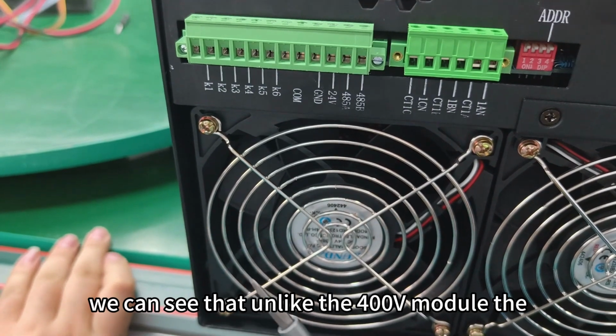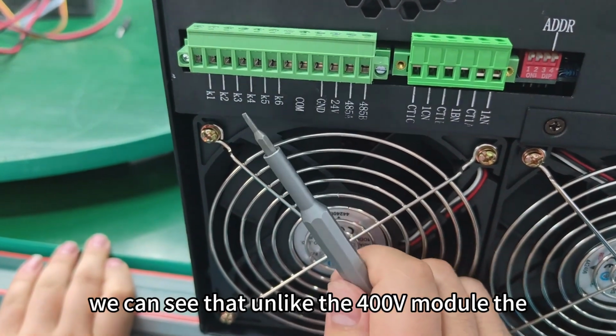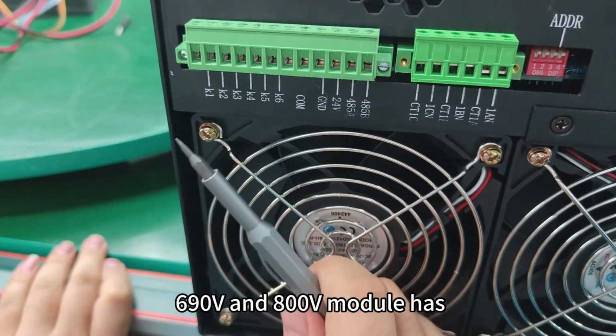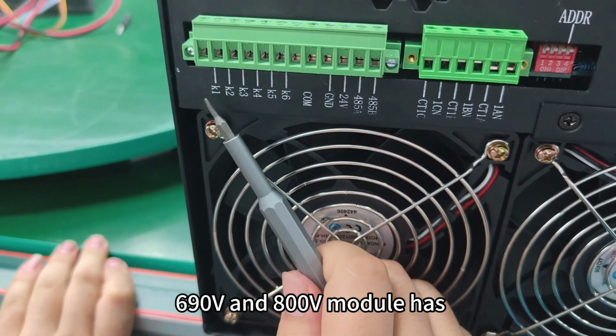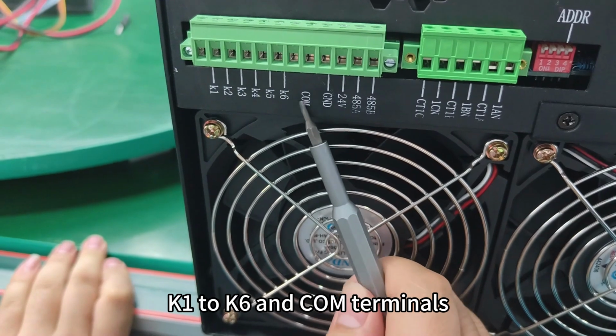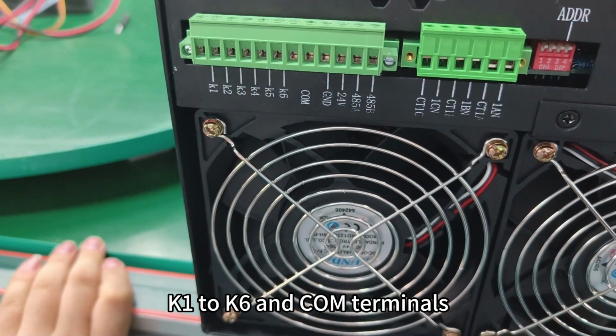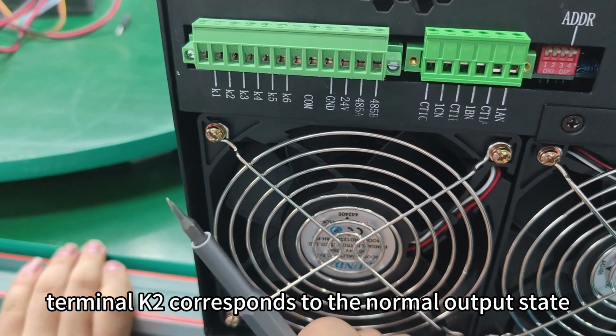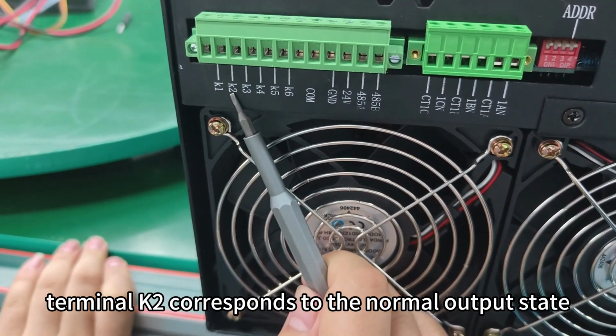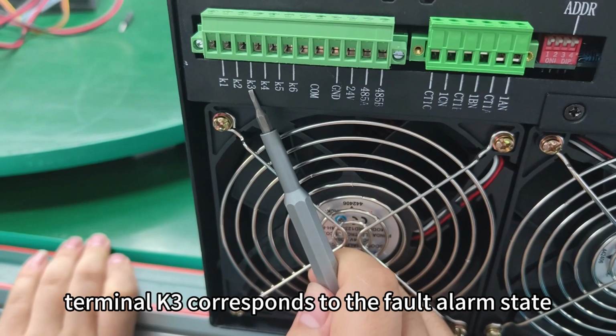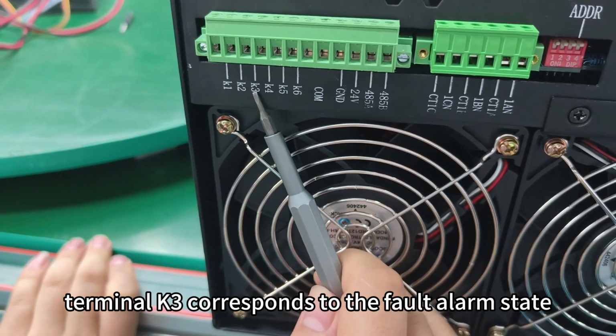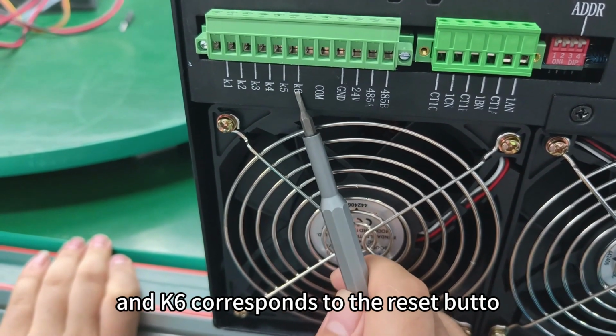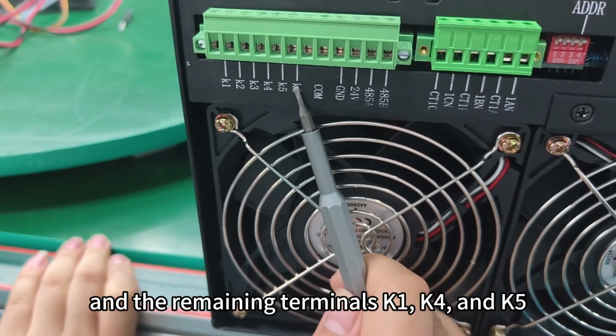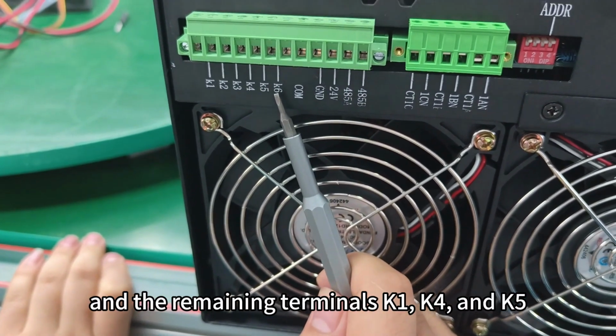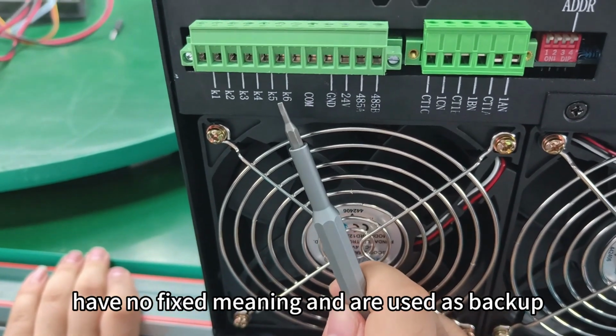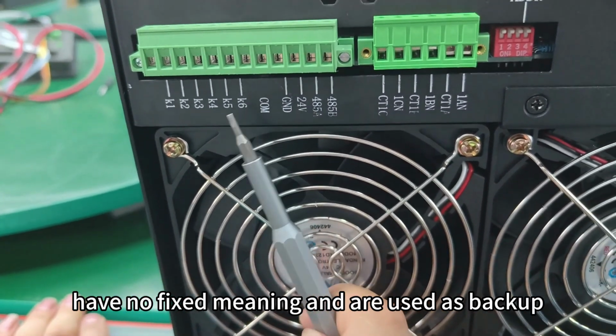We can see that unlike the 400 volts module, the 690 volts and 800 volts module has K1 to K6 and COM terminals. Terminal K2 corresponds to the normal output state. Terminal K3 corresponds to the fault alarm state, and K6 corresponds to the reset button. And the remaining terminals K1, K4, and K5 have no fixed meaning and are used as backup.